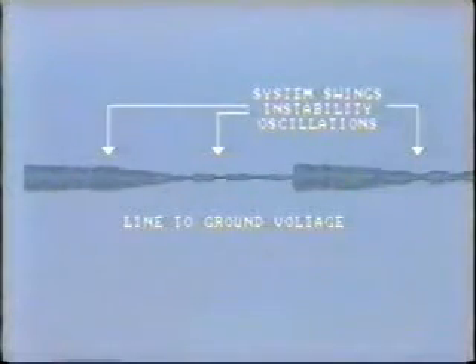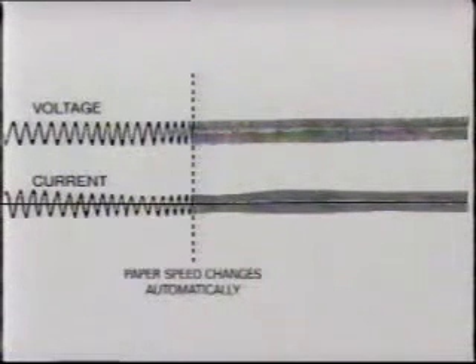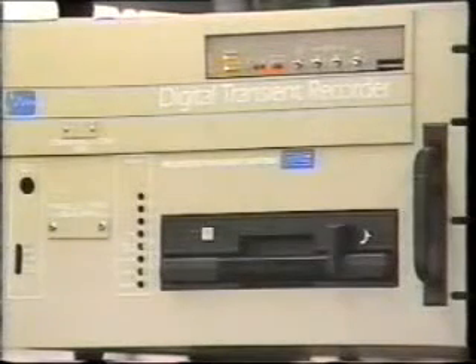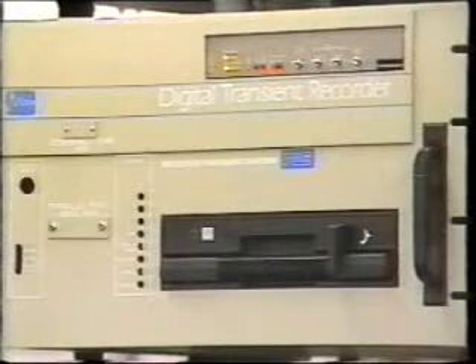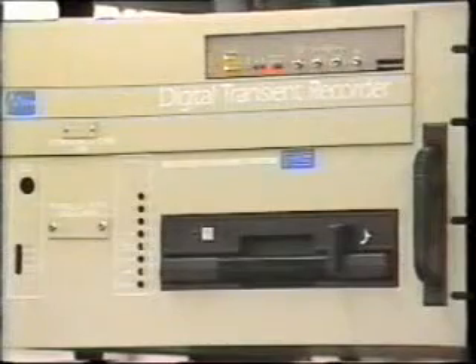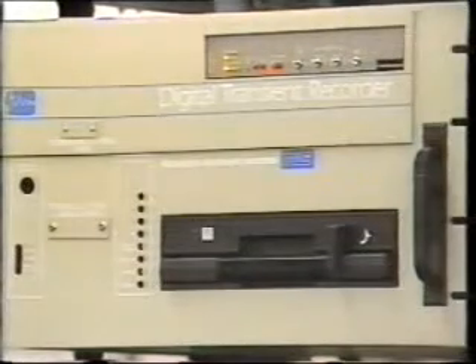System swings, such as those associated with instability, can also be recorded, but such swings may last for several hundreds of cycles and consequently give us a lot of paper to examine. Some oscillographs have the ability to change paper speed automatically when recording these longer-term swings. In recent years, most of the fault analysis systems installed are of the digital type, generally known as digital fault recorders.